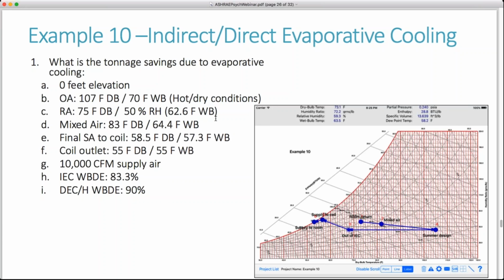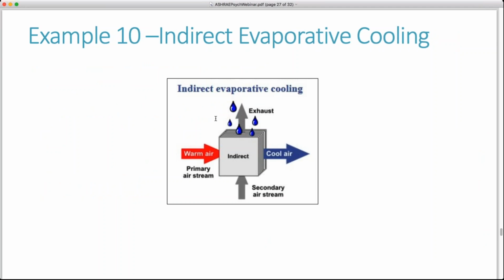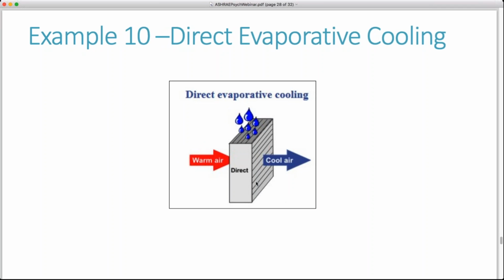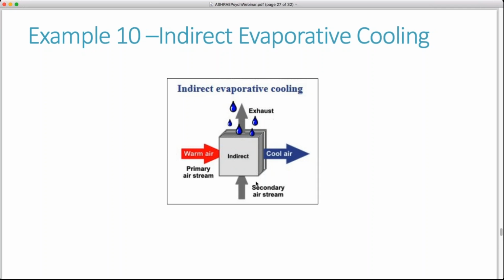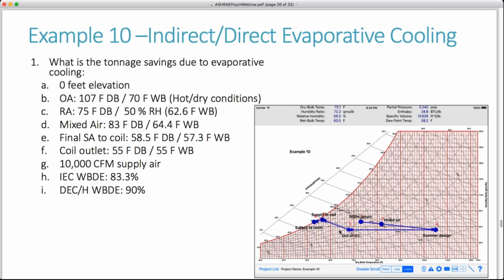So what is direct or indirect evaporative cooling? Well, let me show you a real quick example here. Basically, you're cooling that air, but you're not transferring the latent to sensible. So you're actually using a heat exchanger. In other words, you're using a secondary airstream that is cooled by water, and then that secondary airstream passes through a heat exchanger where it cools the primary airstream. And the cooled air is then circulated by a blower. So you're cooling that air, but you're not taking out the latent heat. And then I already explained to you what direct evaporative cooling is. So a combination of those two is actually quite clever. It allows you to achieve exact psychrometric conditions and save a lot of energy.